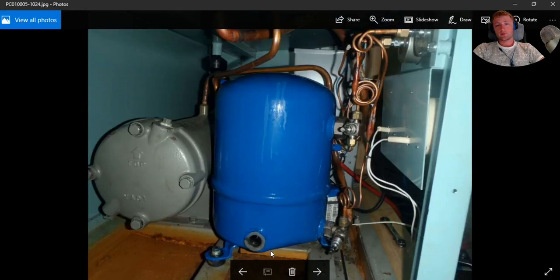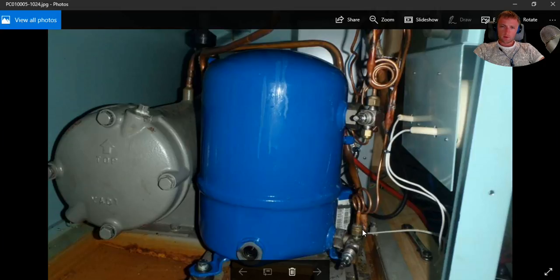And the difference also was here: we can see the oil, we have a sight glass. One moment, here is the suction, this is the cooler. The suction is made by this pipe going here low, and the discharge is here. You can already see the pipe has a smaller diameter. This is the discharge: the freon gas comes in here, it's compressed, and then it turns to liquid. These are the supports for the vibration.